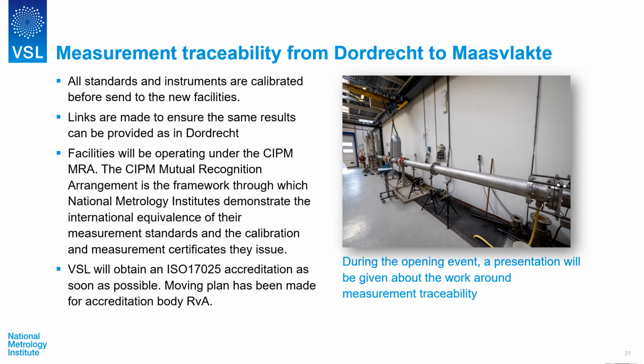Good to know is that all standards and instruments are calibrated before being sent to the new facility. That means they come in with a calibration, even though we can calibrate a lot of them on location. Links are made to ensure the same results can be provided as in Dordrecht.